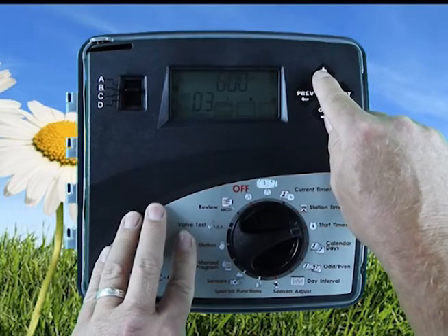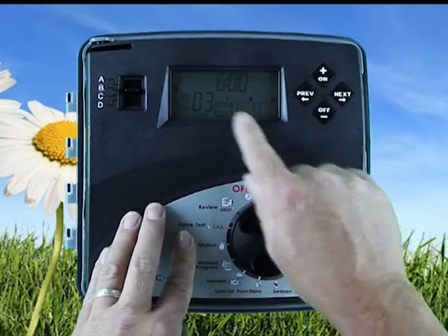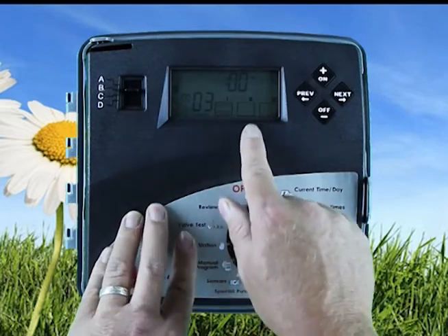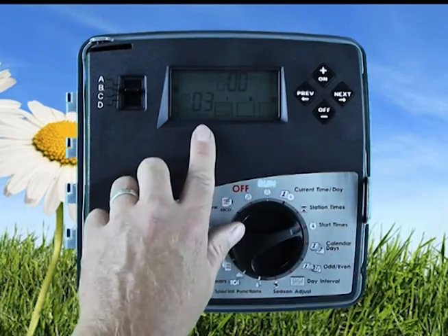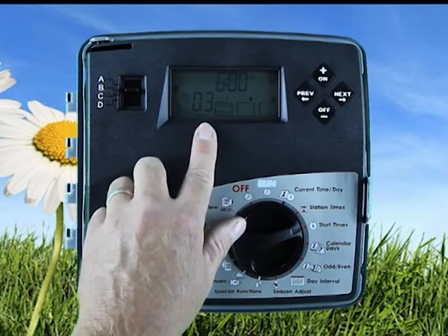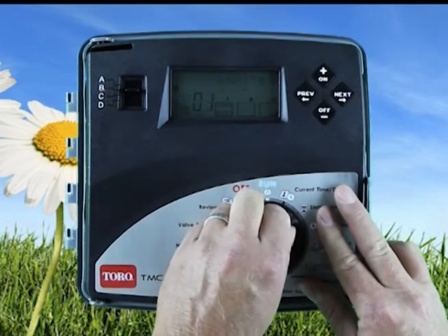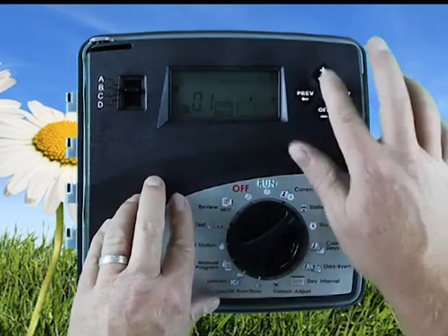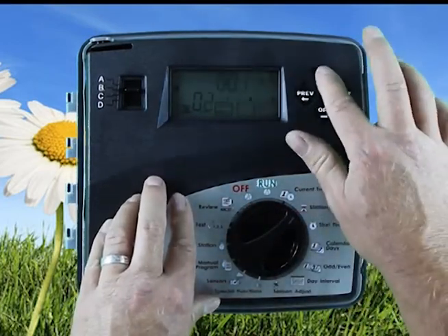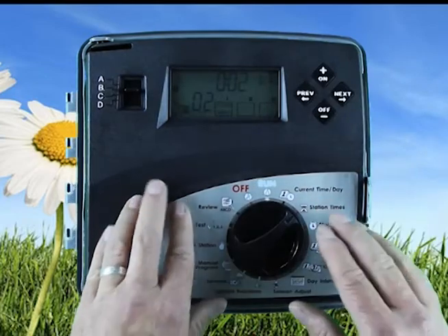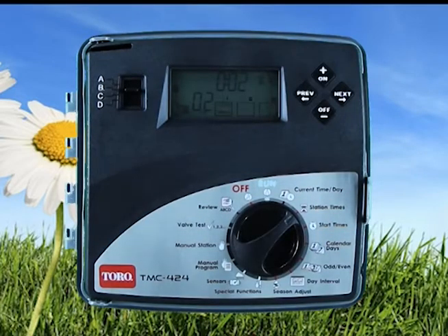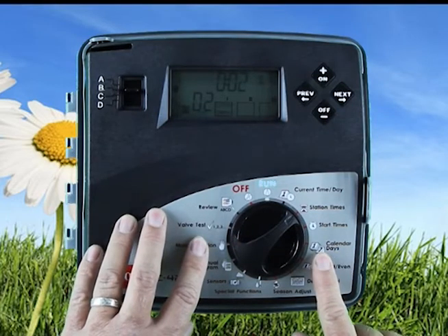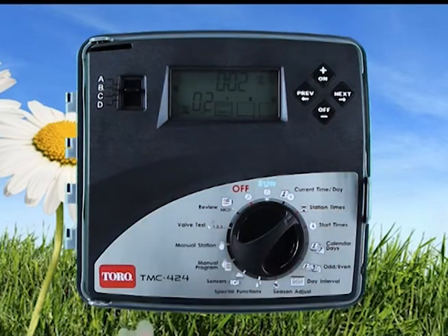And I would have to make sure that I'm not setting it for the same start time as A. So a 6 o'clock a.m. start time for B. That's my third start time. Now, station. As we've seen before, there's nothing selected on there. I'd have to put some time on each station to run a B station. Just like a separate controller. You'd have to go to calendar days, set the days you want on or off, start times and station times.